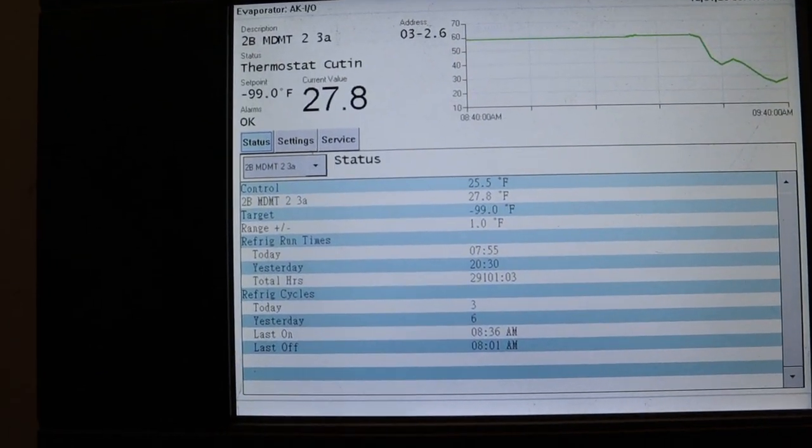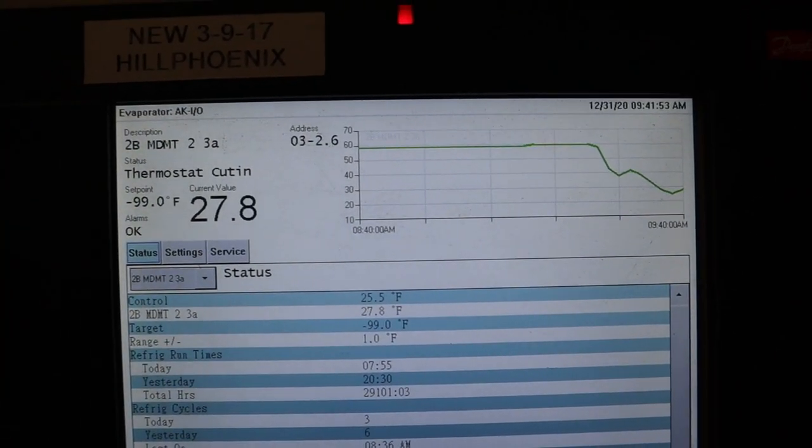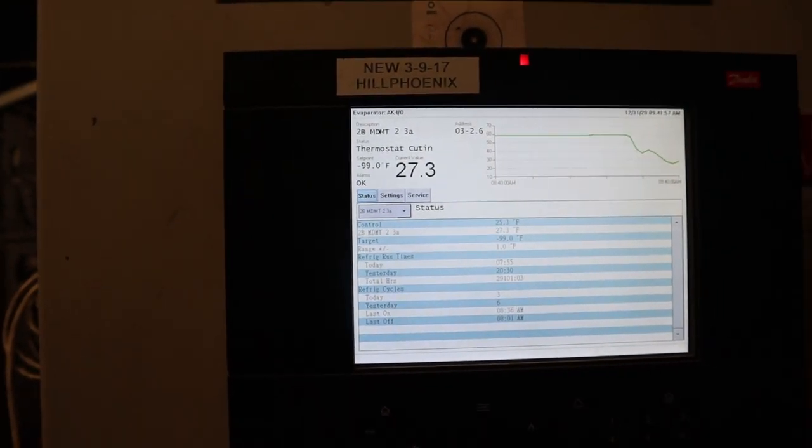27 degrees, so we're good with that. Everything works, we already double-checked it. It will hold in defrost and it'll turn back on without bleeding by. Now to check out the cases - yep, 25-26 degrees, we're all set.